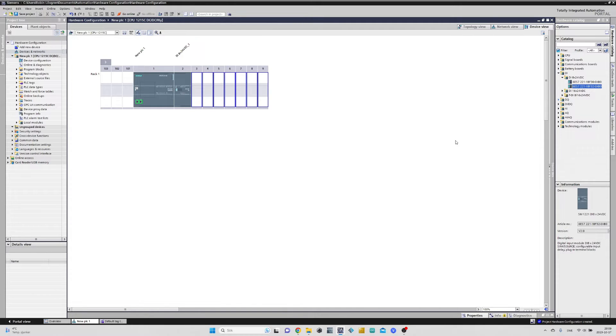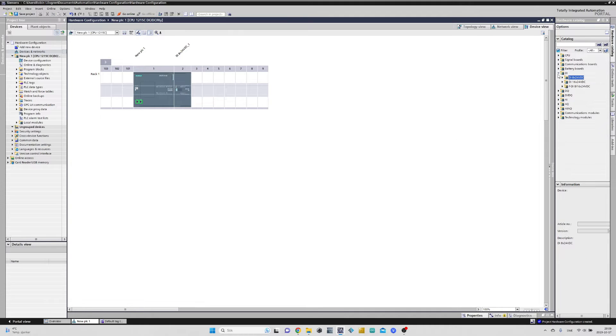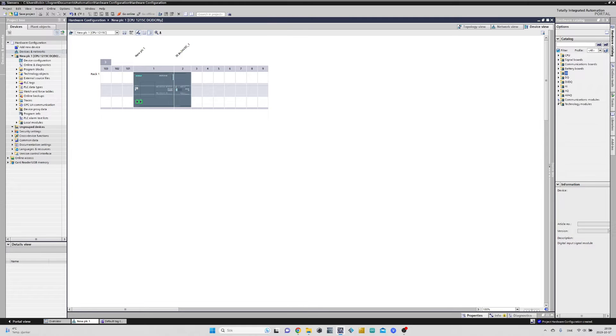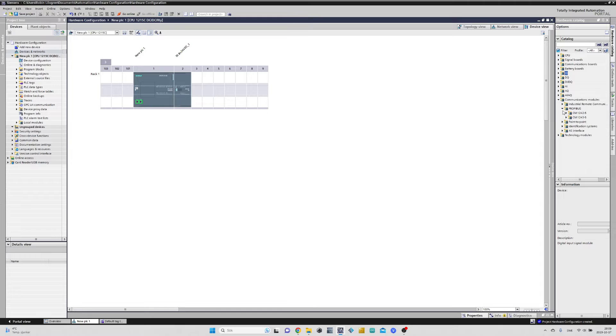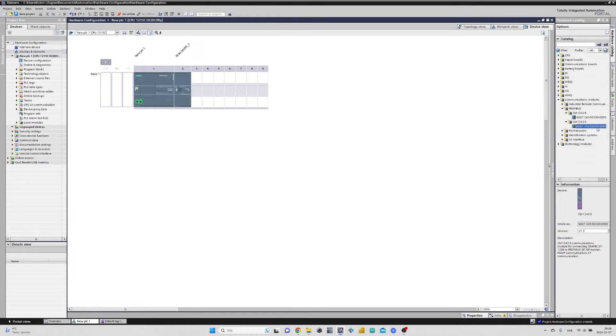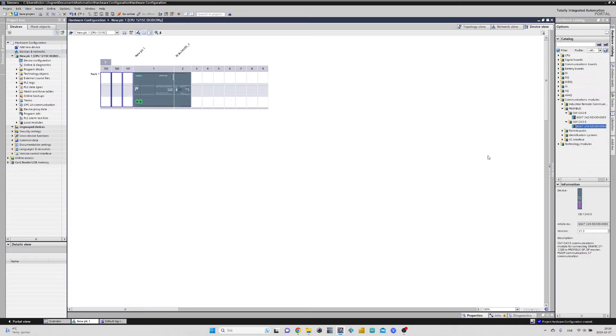Let's add something we can use on the left side of it too. I will add a Profibus Master communication module. As you can see now that I click on this one, only the left side of the CPU's rack will be selected. That means I can only connect the communication module to the left of the CPU.